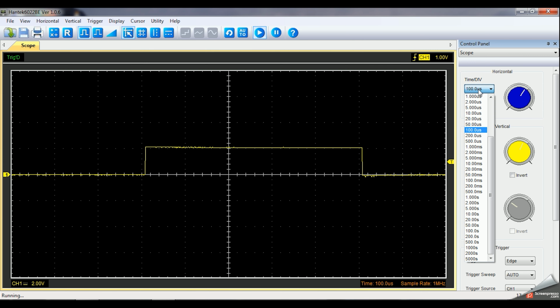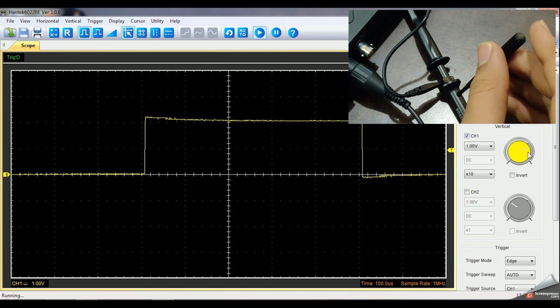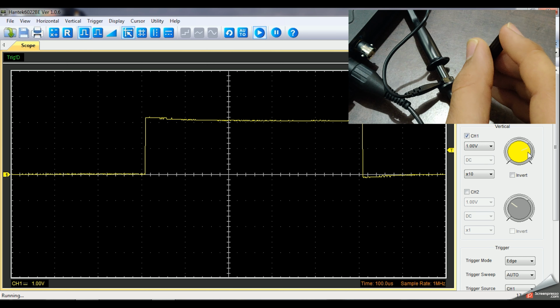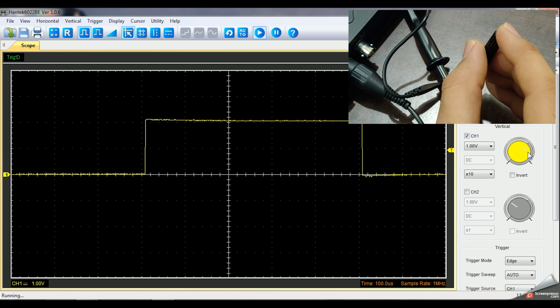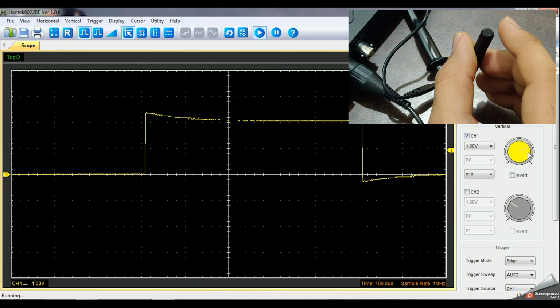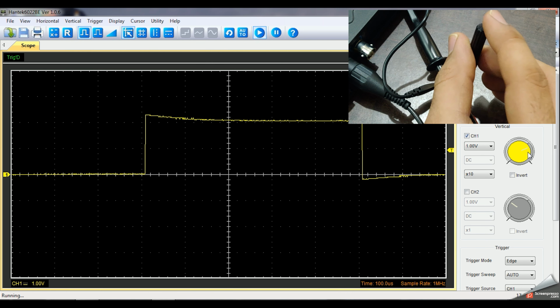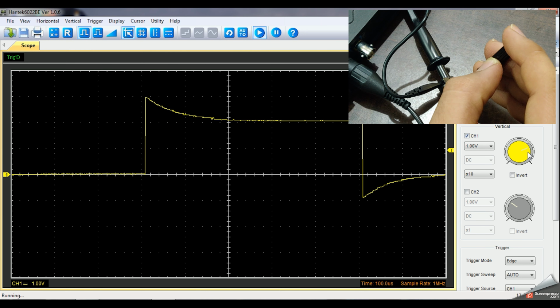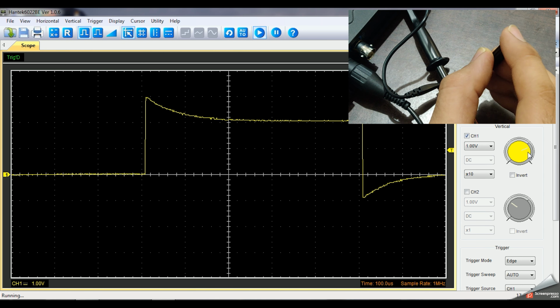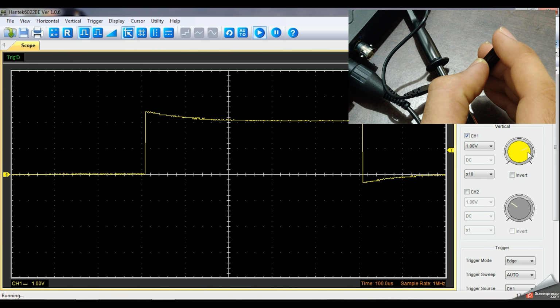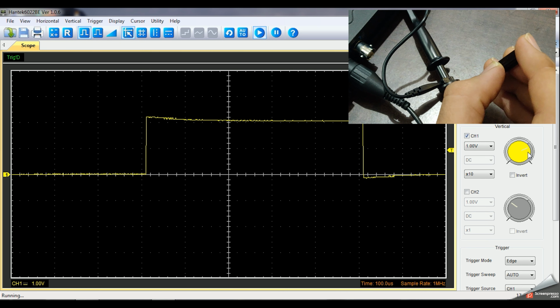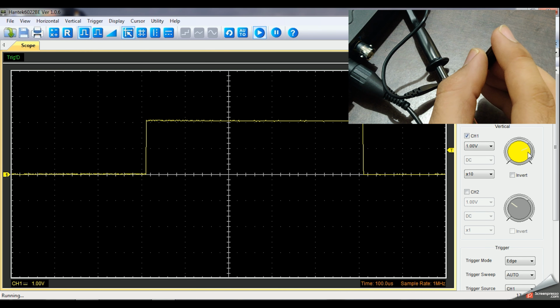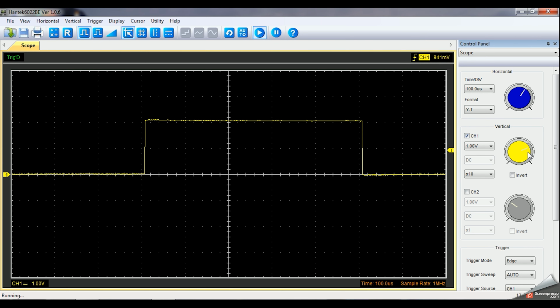Once all the values are set, now you can start the tuning, the calibration of the probe. You can use a screwdriver and just start rotating the screw. You can see on the screen the variation of the square waveform. You should always make sure that you have very linear lines on the top and bottom. Now I'm just trying to adjust the screw. You can see I'm trying to make it flat. Yeah, now it's almost flat. So this is the right way of calibrating.